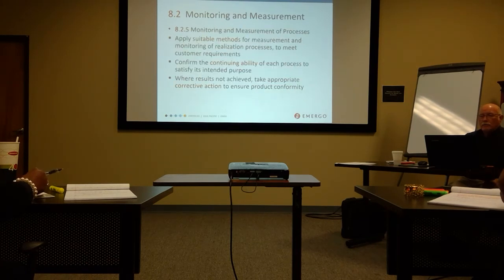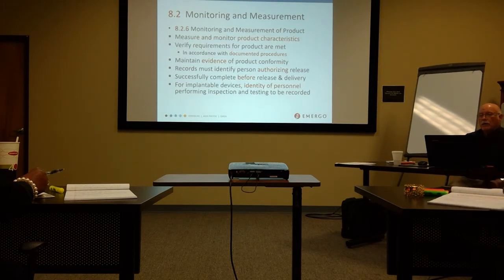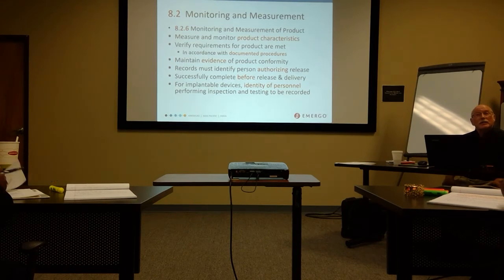We're going to get to CAPA in a second. That's all good. Monitoring and measurement of process, we have lots of different ways to do that. Product characteristics is all part of chapter 7, in terms of how do I know what product met its requirements, because I have all this test data that says it does. It's part of finished device acceptance. Finished device acceptance, by the way, you're not going to find a whole lot of in ISO because that is a country-specific requirement. You should have a procedure, whatever inspection you do, and make sure that's documented. The regulatory requirement is whoever releases that device to distribution and sale, make sure you get that person's signature and date. My suggestion would be that really ought to be QA for your MR, not the warehouse person.